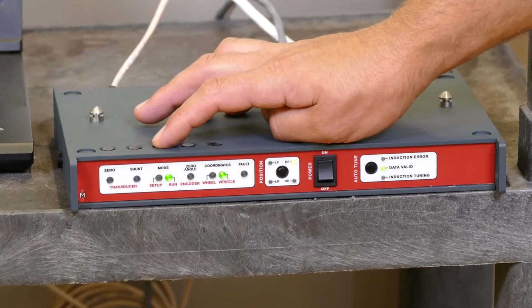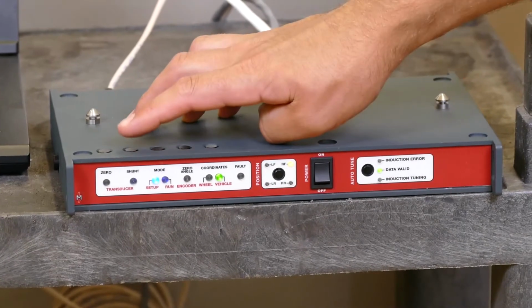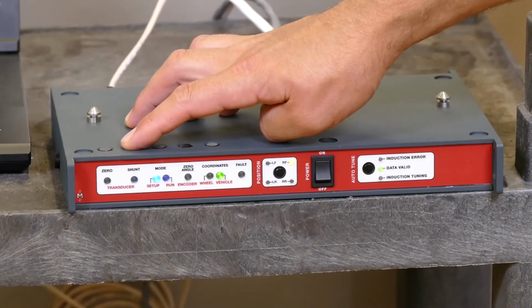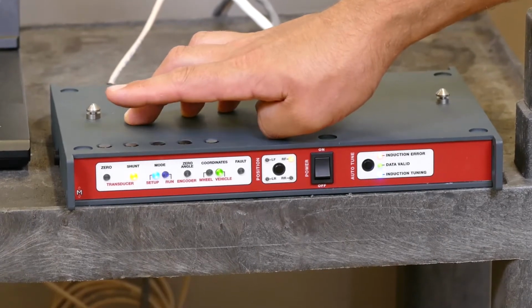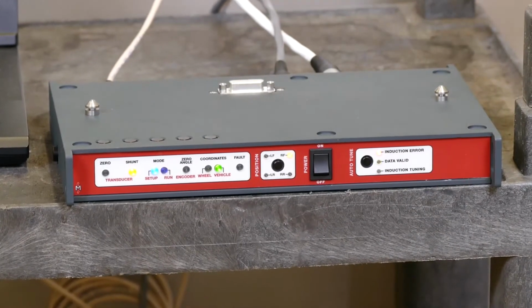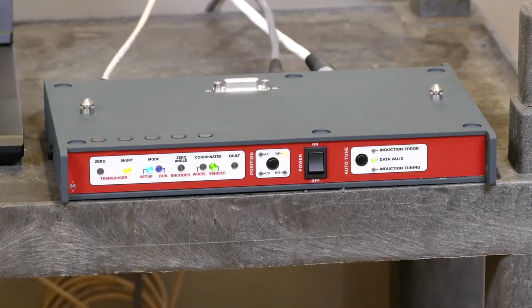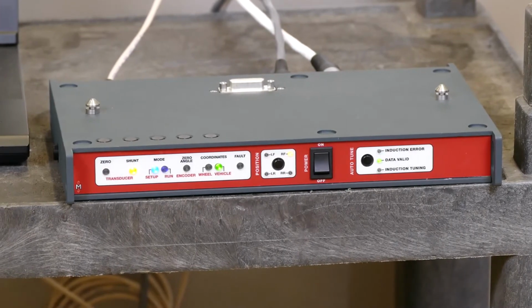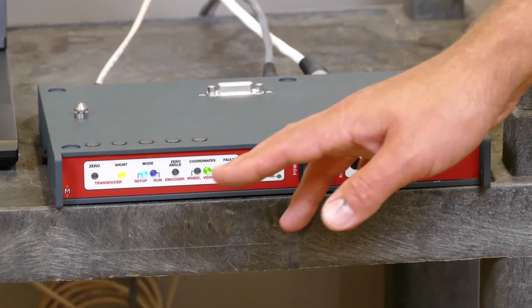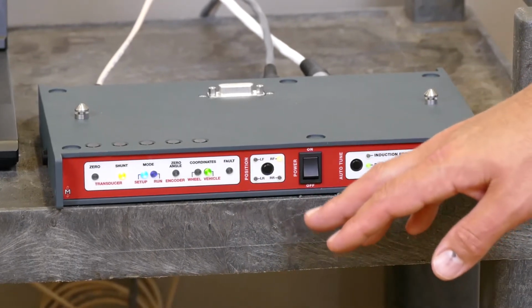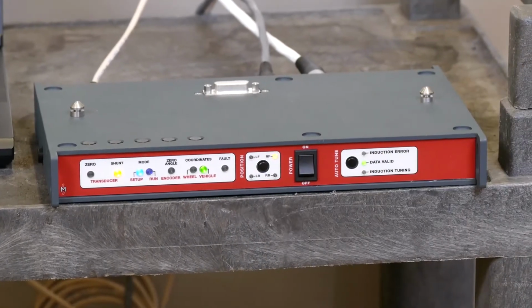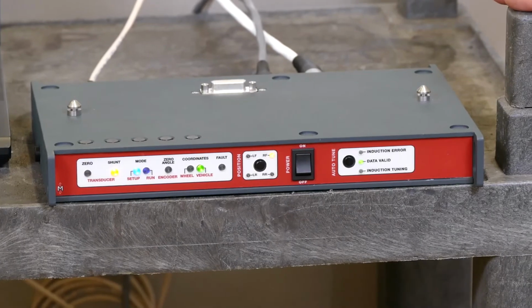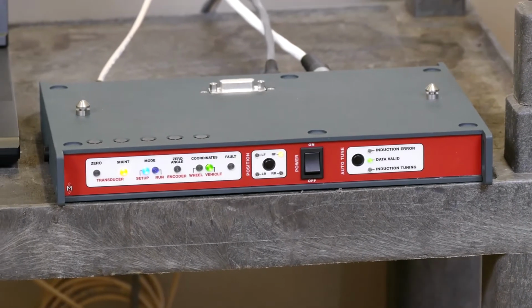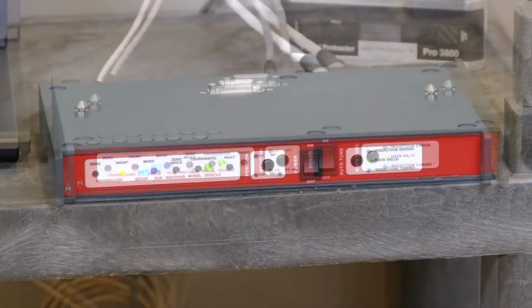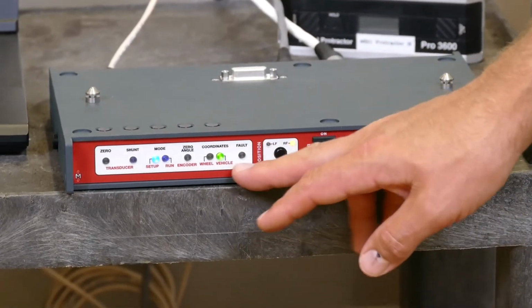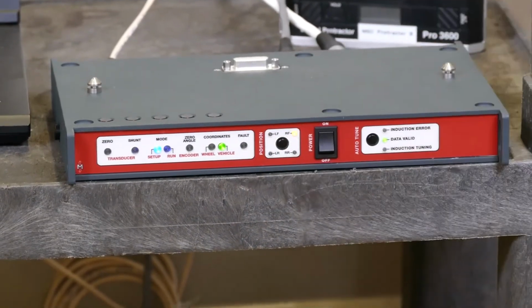So we're going to go from run mode to setup mode. And the first step is to do the shunt sequence. So we press the shunt sequence, and it's going through the shunt calibration sequence. So if this shunt sequence finishes and the fault light does not come on, then it has passed the sequence and the shunt calibration is within 2.5% of the factory shunt calibration. The shunt sequence is finished. The fault light did not come on, so it's passed the shunt sequence.